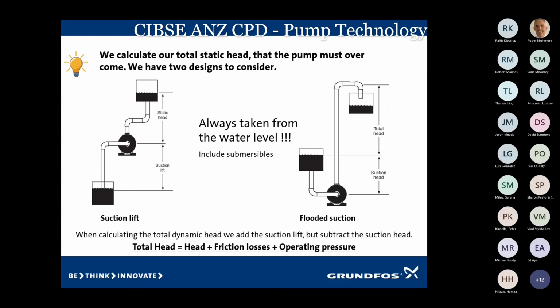Just one thing to note, when you have a submersible borehole pump sitting in a well, you might have the pump sitting at 200 meters down the well, and when the well driller comes along, he'll generate the given flow that we're looking for. So he'll purge the well. The water table might be sitting at 5 meters below the ground, but when he pumps it down, he generates the flow rate that we're looking for. He might pull it down to 100 meters.